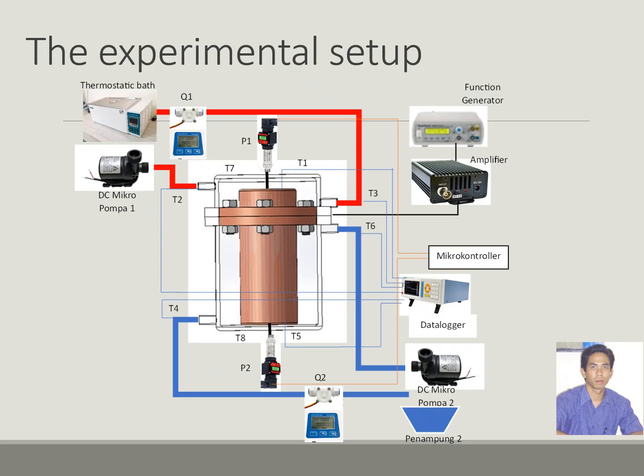With the circulation system, the system operates using two fluid loops. Hot fluid loop, red line: heated water is supplied from temperature control water baths and circulates using a micro DC pump. The hot fluid enters the upper section of the heat exchanger and transfers heat to the copper core. Cold fluid loop, blue line: cooling water at approximately ambient temperature, 25 to 30 degrees Celsius, is circulated through a separate channel using another micro pump, removing heat from the system.